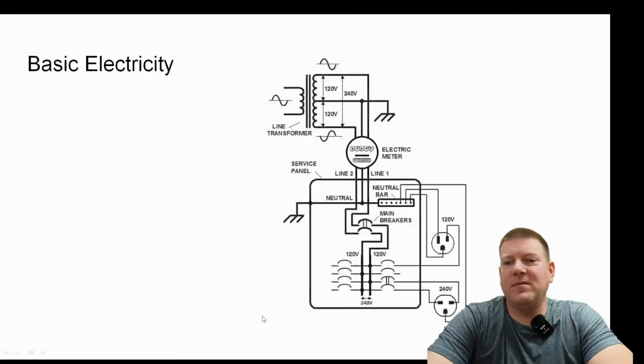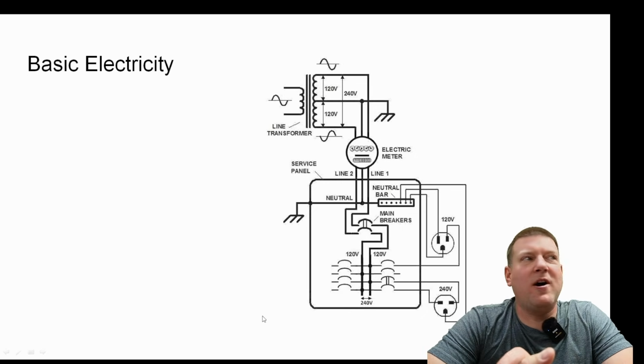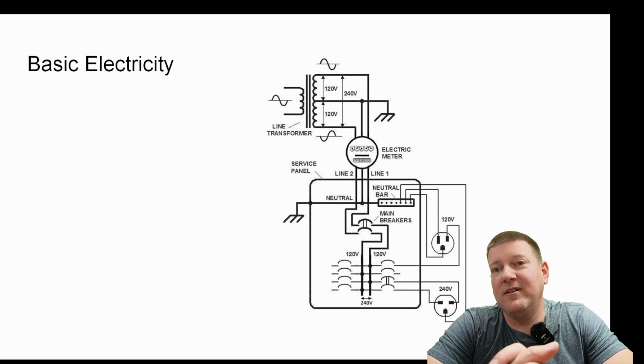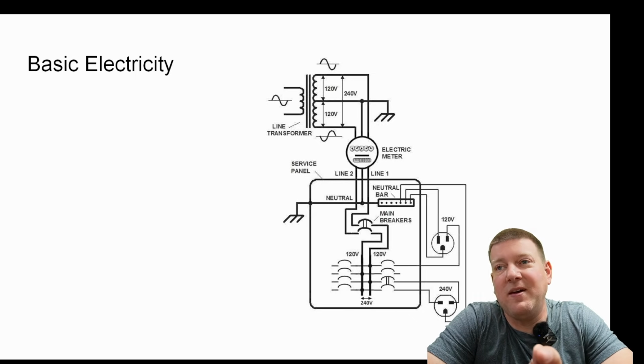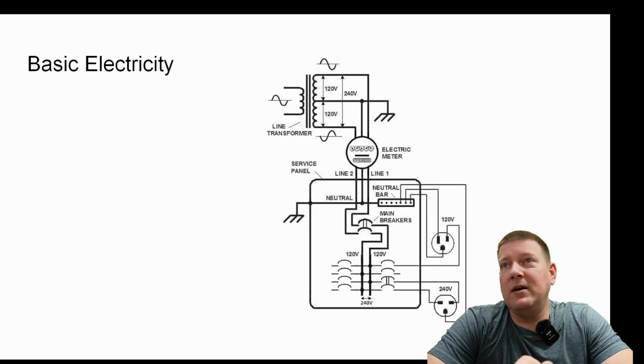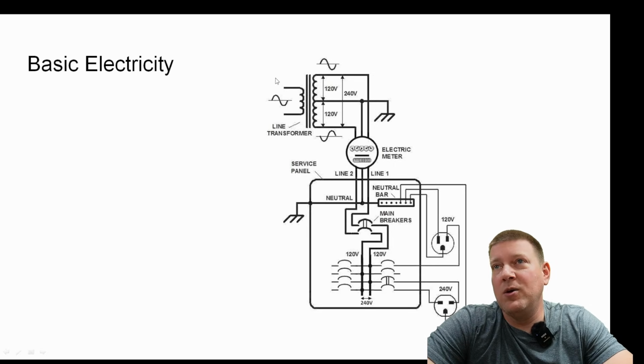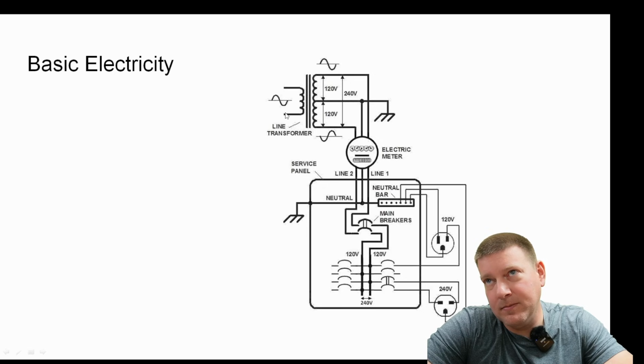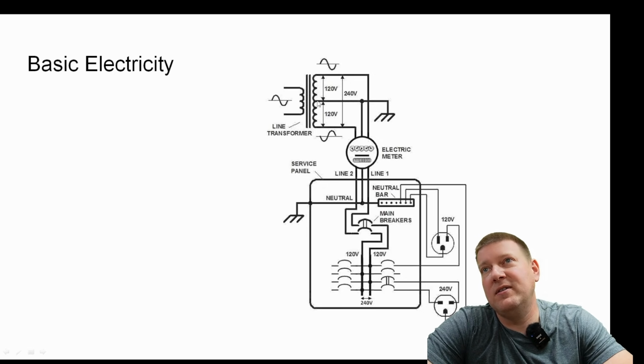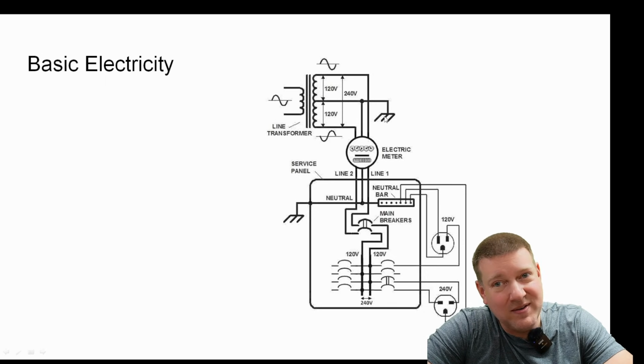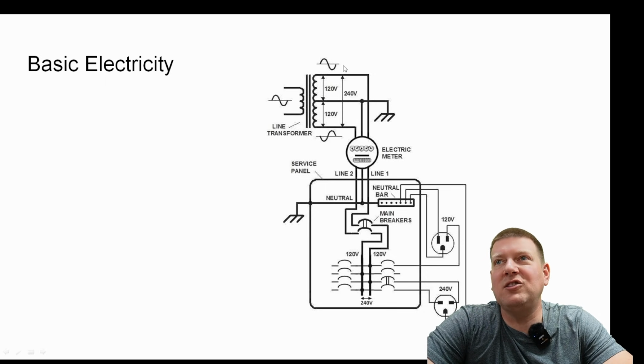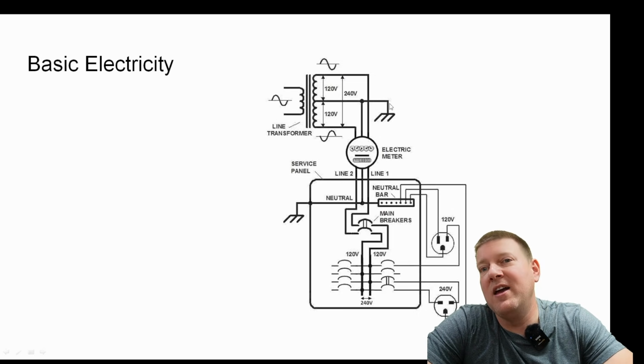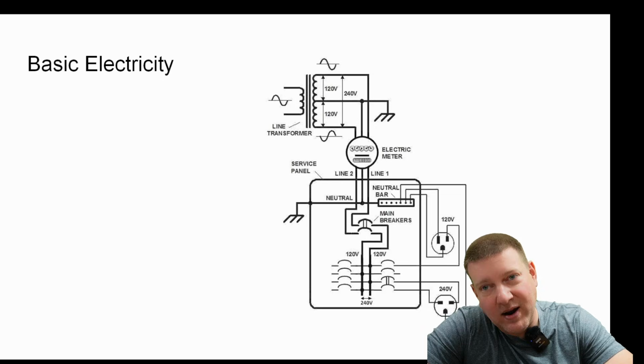All right, folks. So we're going to kick this one off and we're going to talk about 120 volts, okay? So in American power systems, we have something called the split phase, whereas we have the line coming in, and then we have a secondary, which is tapped in the middle to ground. And that means that each leg, 120 volts here and 120 volts here, each leg is referenced to ground.